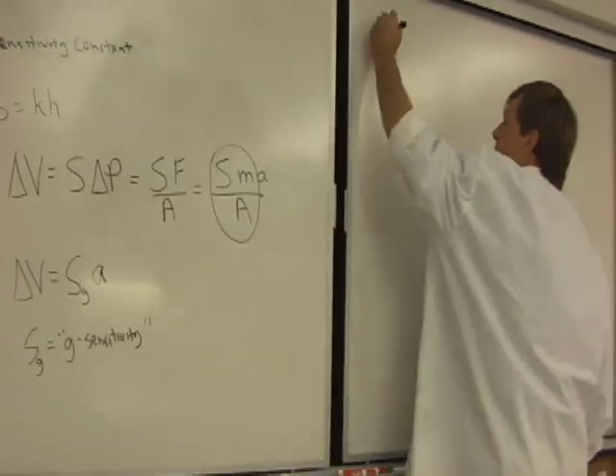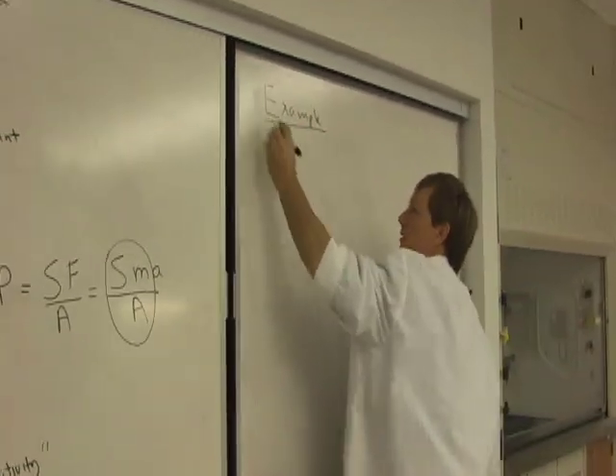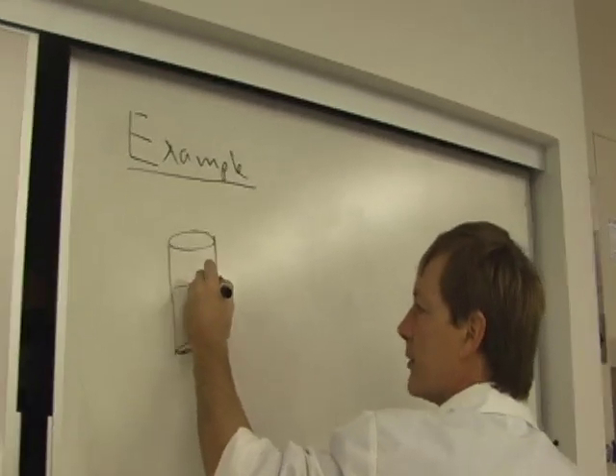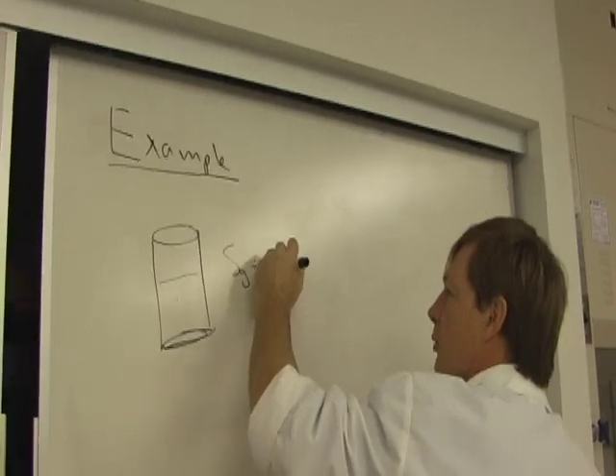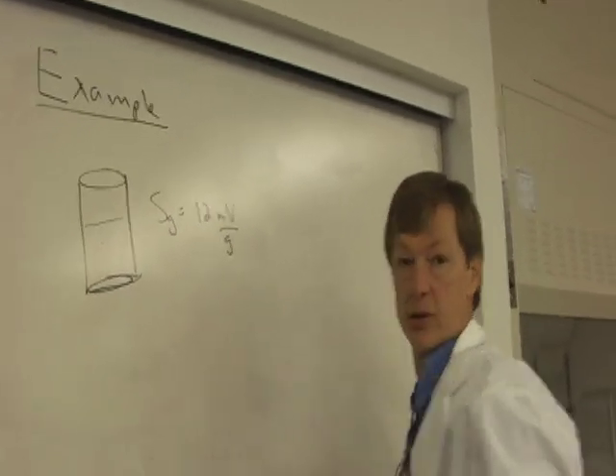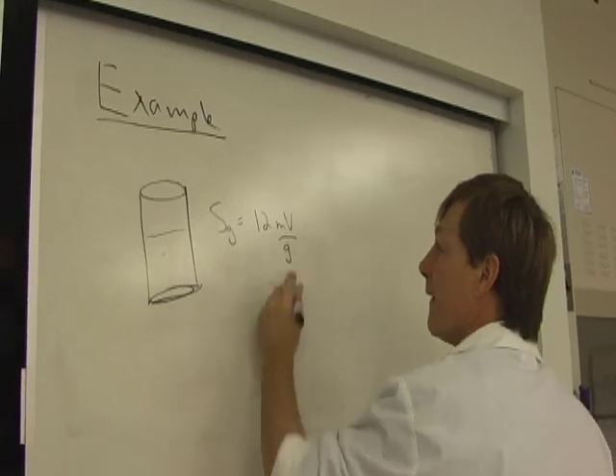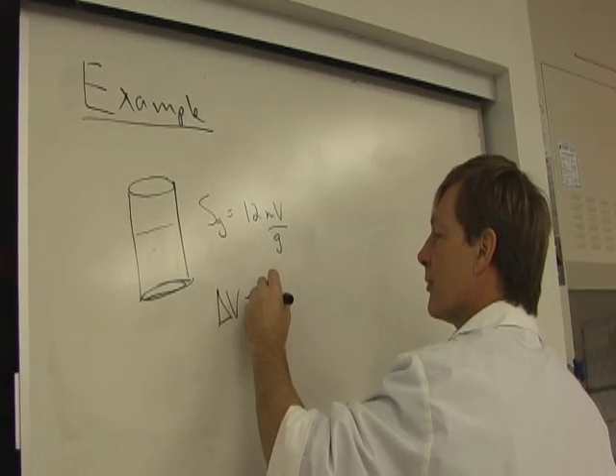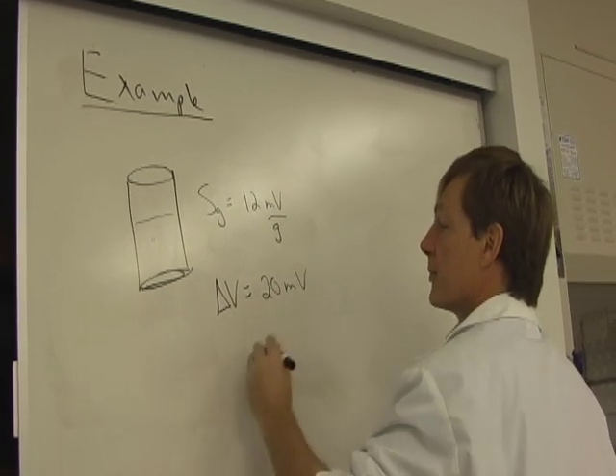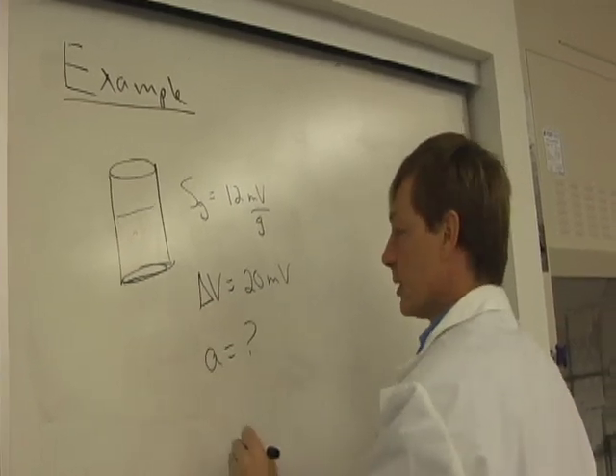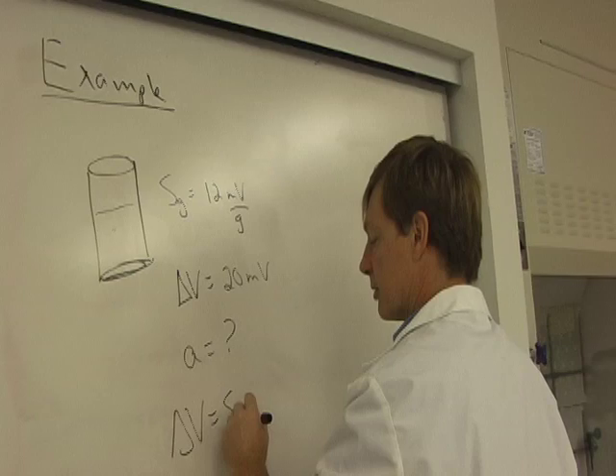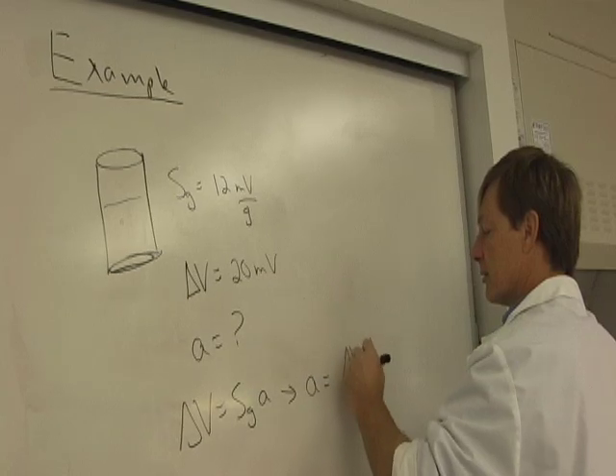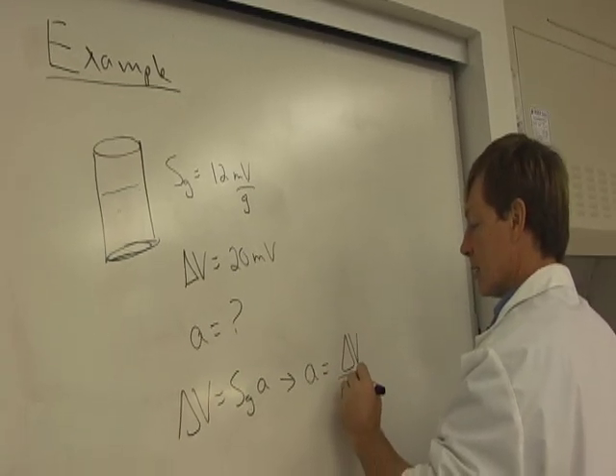For example, let's say I've got this accelerometer here, and I read, and it's got a g sensitivity of 12 millivolts per g. And g is, like I said, a unit of acceleration. And I get a reading, a voltage reading, of 20 millivolts. And I want to know, what's the acceleration? Well, voltage is equal to g sensitivity times acceleration. So the acceleration is equal to the voltage measured divided by the g sensitivity.